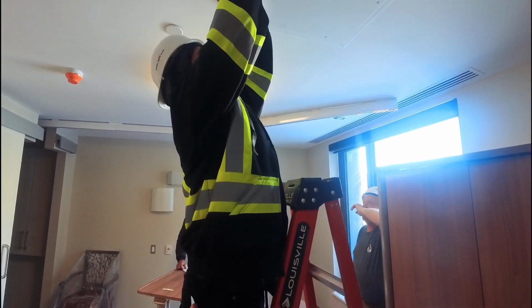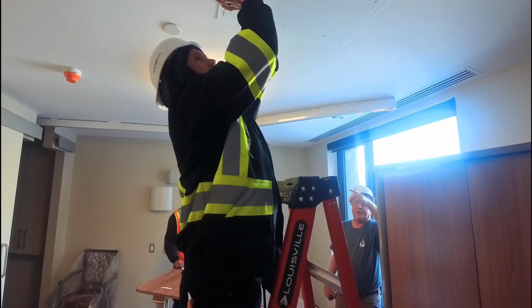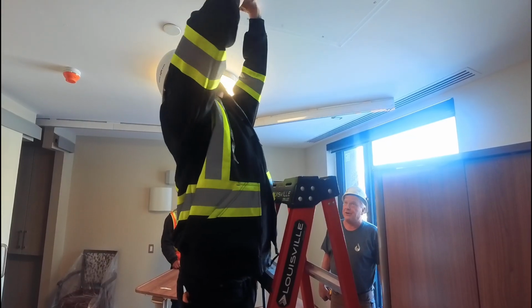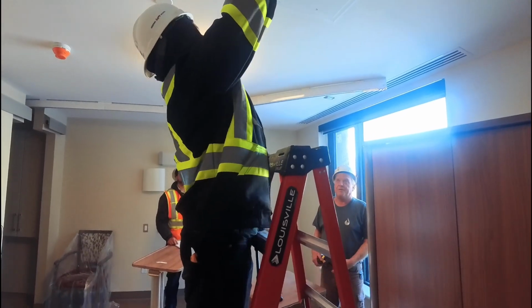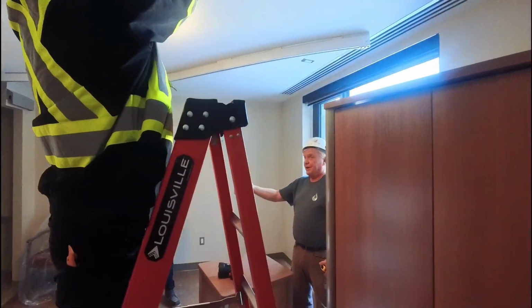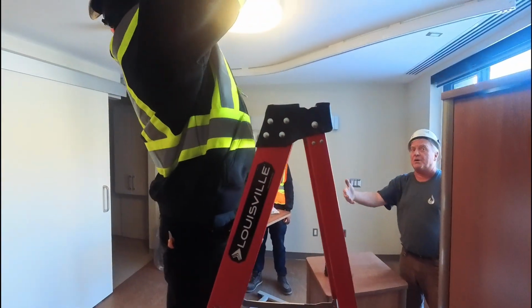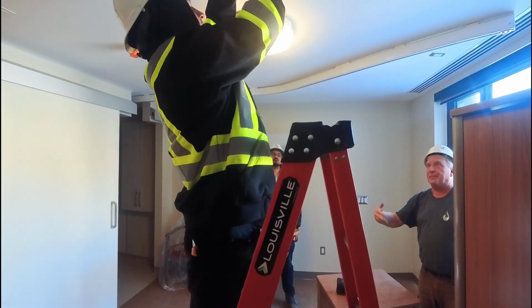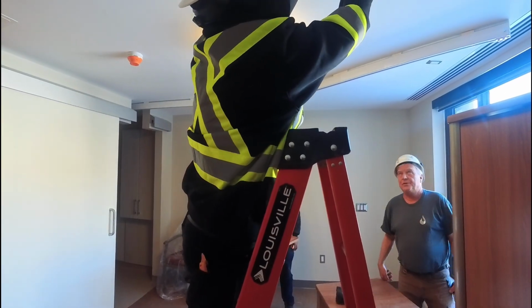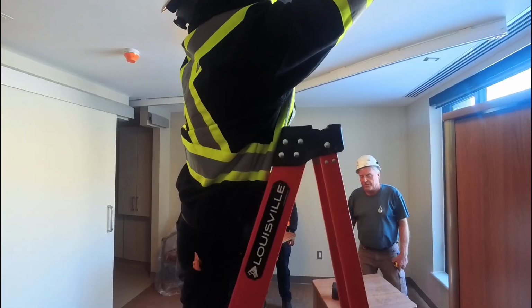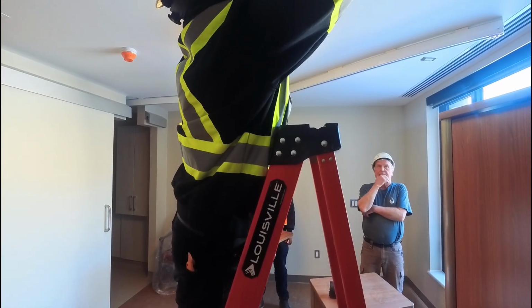Unless it's a cleaning as you're doing, because those coils could get dirty with just plain dust too. You could stick a vacuum cleaner head in there with a small soft brush on it. And just brush off them electric heating coils, the same as you would an air conditioning coil or something like that. Just a soft brush.